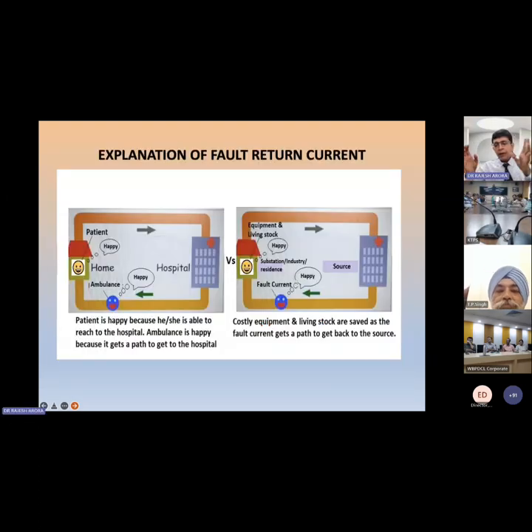When you give way to the ambulance and the ambulance reaches the hospital, the patient and the family members at home feel happy. Similarly, if you provide a proper design of the earthing system and a path for that fault current to reach the source in the minimum time, the power system in charge, substation in charge, industry in charge, building in charge, family owners, and factory owners will be happy. You can avoid that fire scenario because of short circuit.